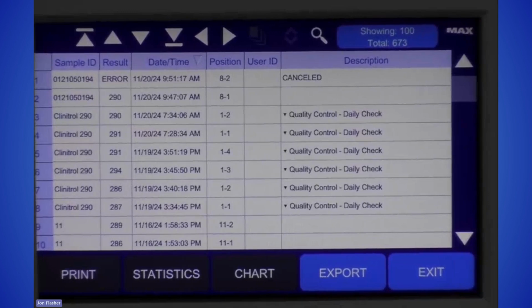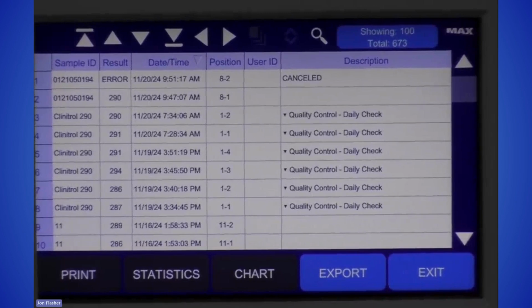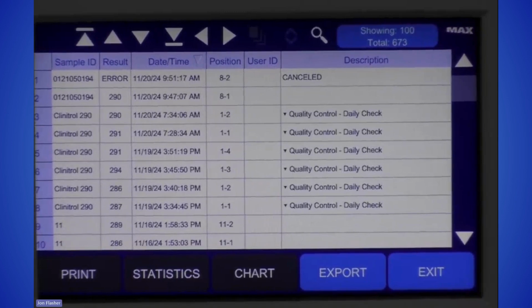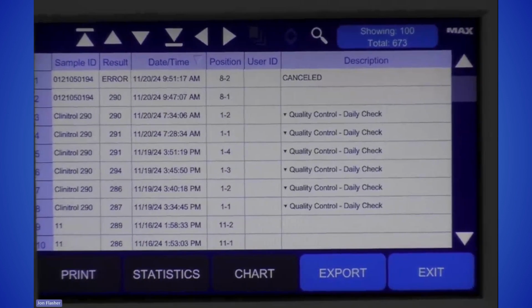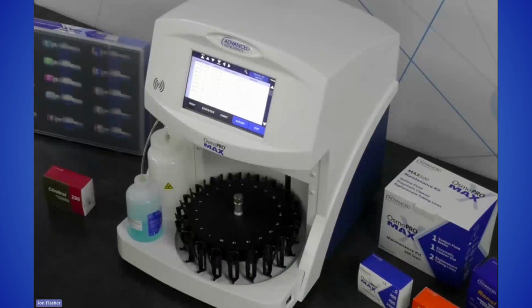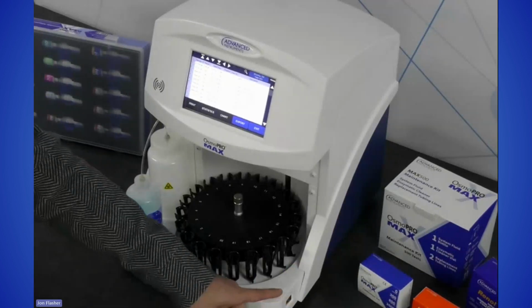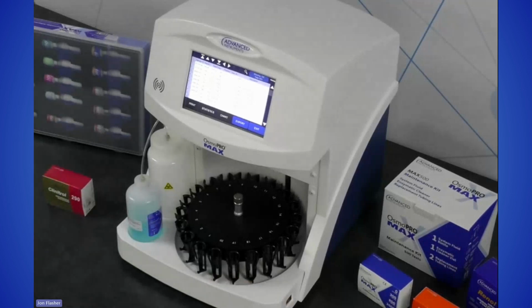In your result log, you can see a log of all of the results that were performed on the instrument over a span of the last 1,000 tests. We can store up to 1,000 results and 10,000 instrument events within this software. So you have leeway of about 1,000 results before you need to consider whether you're saving the paper copies from an external printer, or backing this up on some hard drive by exporting the data, because that's also a feature. You can see this little export button right here, and you can use the USB port on the side of the instrument to export whenever you're ready.